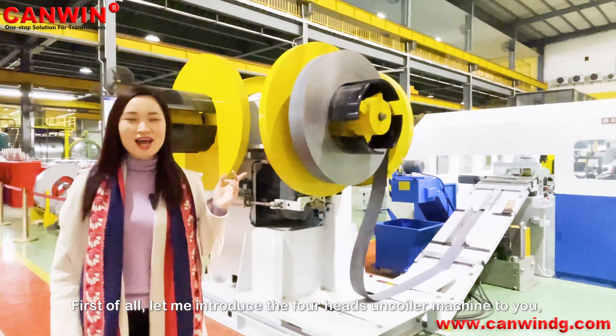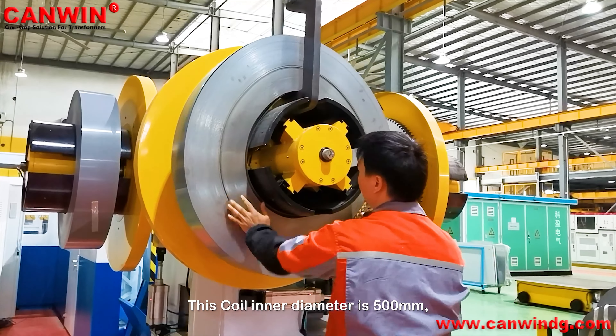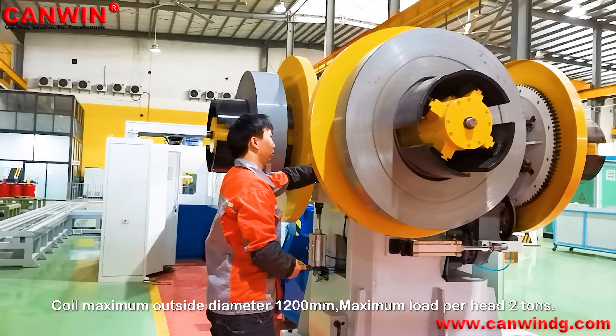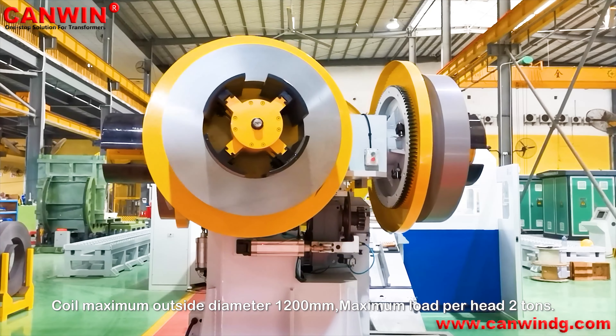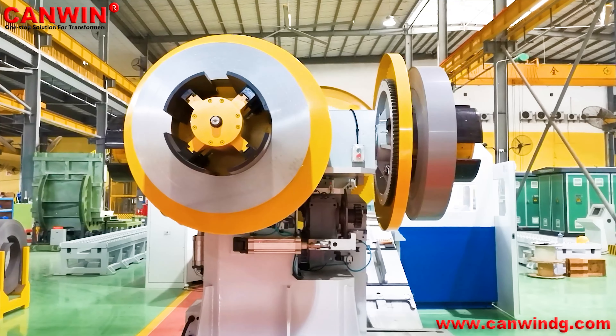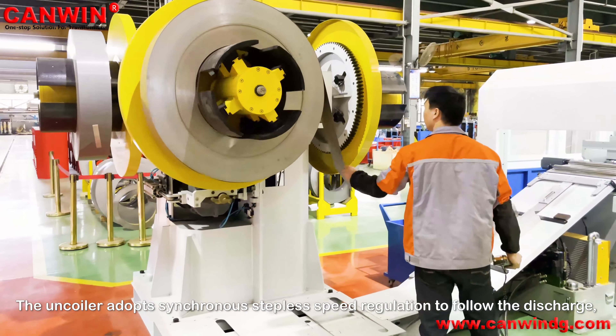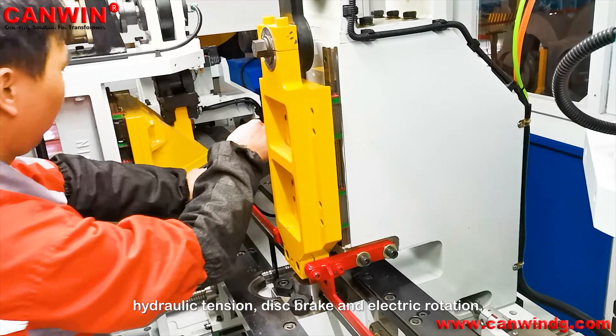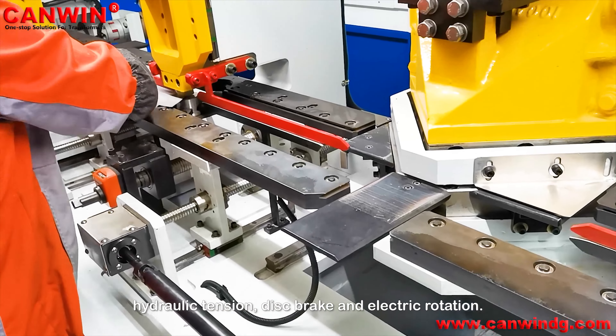First of all, let me introduce the four heads uncoiler machine. This coil inner diameter is 500 mm, coil maximum outside diameter 1200 mm, maximum load per head two tons. The uncoiler adapts synchronous doubling speed regulation to follow the discharge, with hydraulic tension, disc brake, and electric rotation.